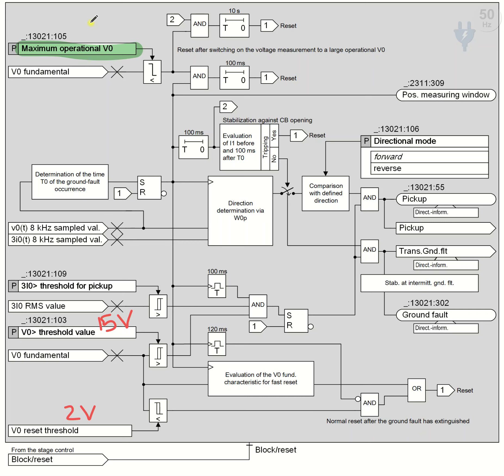In the previous session we discussed that if the system is a radial system, we give 3 volts as a maximum operational zero sequence voltage.